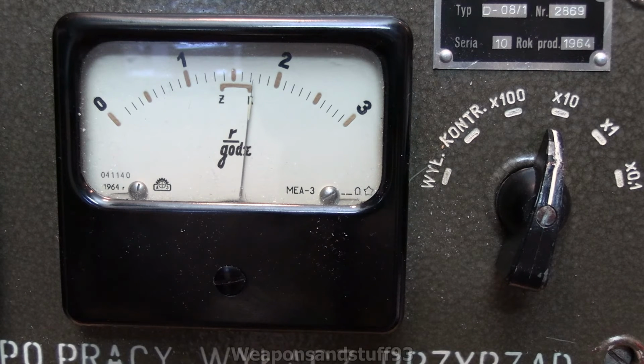Again, I don't think the calibration on this is completely correct. When I've had this turned on for about an hour previously and then done tests with it, I've had it read very similar with the same sources next to the DP2. So I'd assume this is pretty accurate. If you have fully charged batteries in it, you leave it on for quite a bit to dry out. Obviously in theory you shouldn't be running it like I'm running it with the bottom bit open. But as I said, the bottom bit was rusty and I actually wanted to demonstrate this because, for safety reasons and legal reasons and whatever, I don't randomly have gamma sources that can go high enough to register on a multi-Rontgen scale.